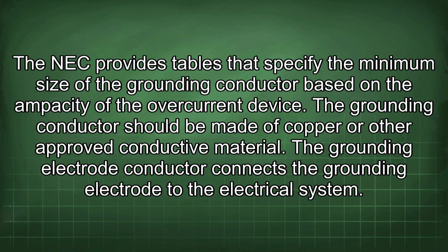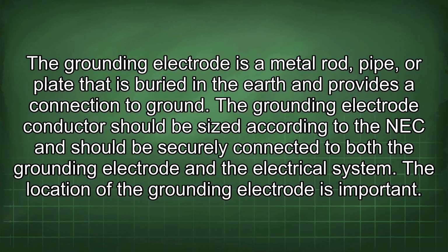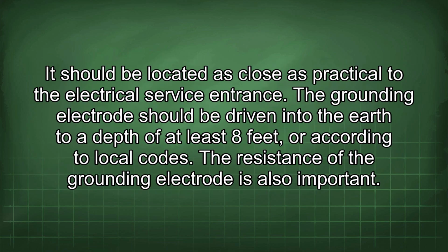The grounding electrode conductor connects the grounding electrode to the electrical system. The grounding electrode is a metal rod, pipe, or plate that is buried in the earth and provides a connection to ground. The grounding electrode conductor should be sized according to the NEC and should be securely connected to both the grounding electrode and the electrical system. The location of the grounding electrode is important. It should be located as close as practical to the electrical service entrance.